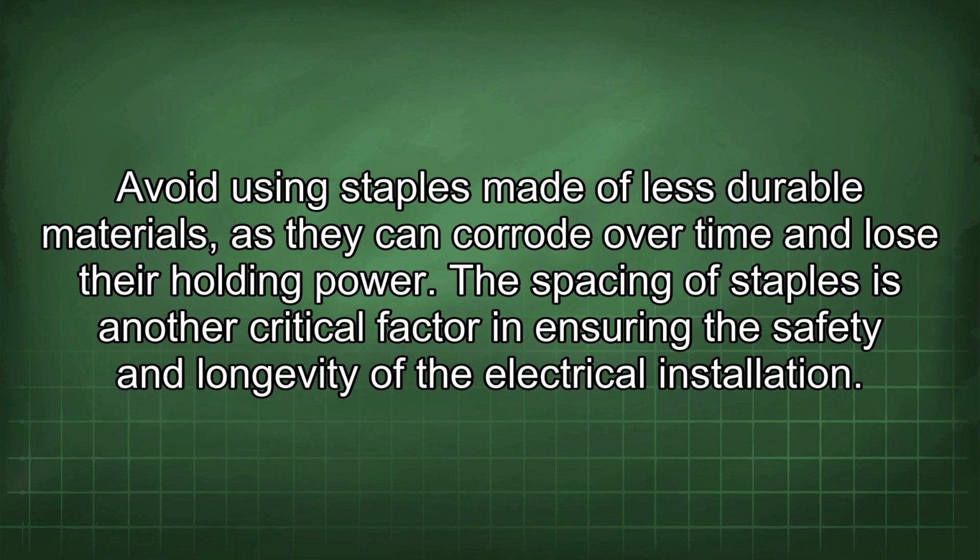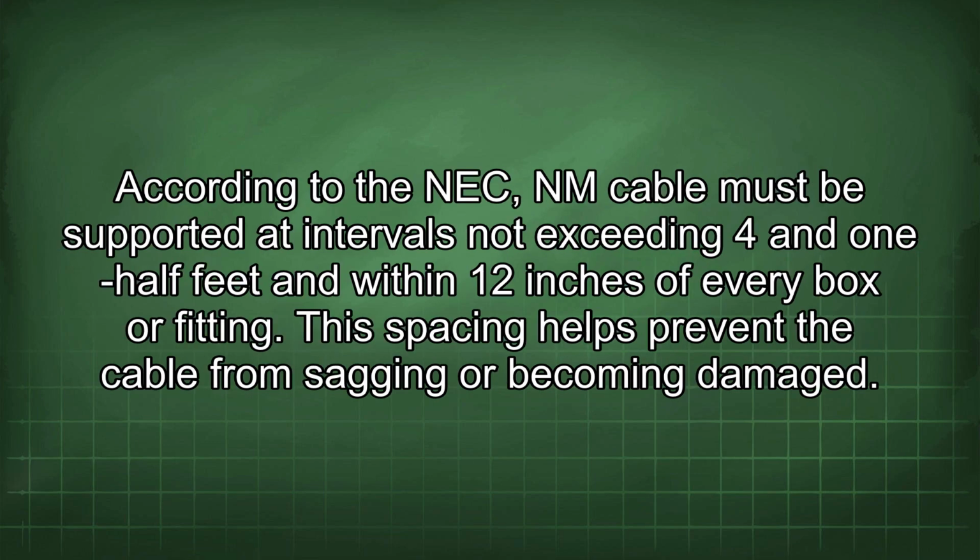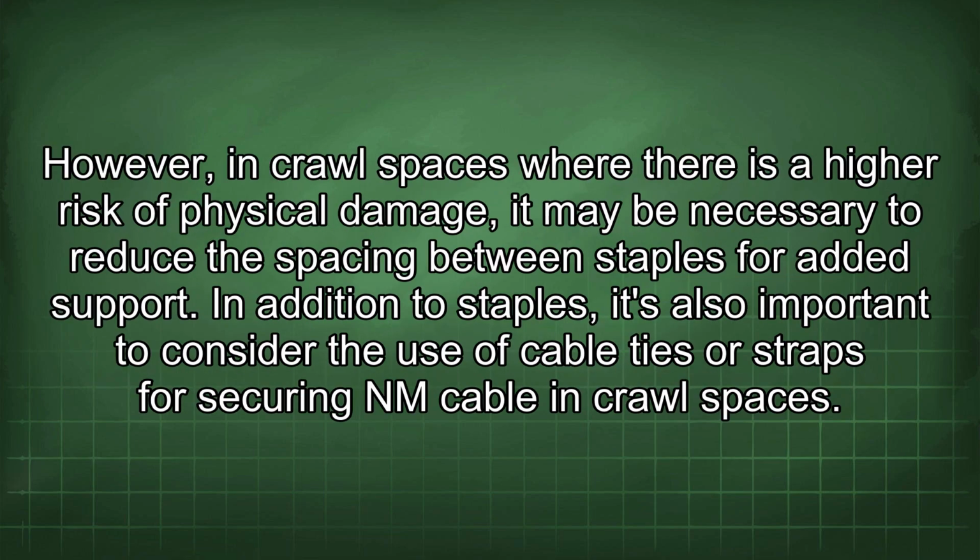The spacing of staples is another critical factor in ensuring the safety and longevity of the electrical installation. According to the NEC, NM cable must be supported at intervals not exceeding 4½ feet and within 12 inches of every box or fitting. This spacing helps prevent the cable from sagging or becoming damaged. However, in crawl spaces where there is a higher risk of physical damage, it may be necessary to reduce the spacing between staples for added support.